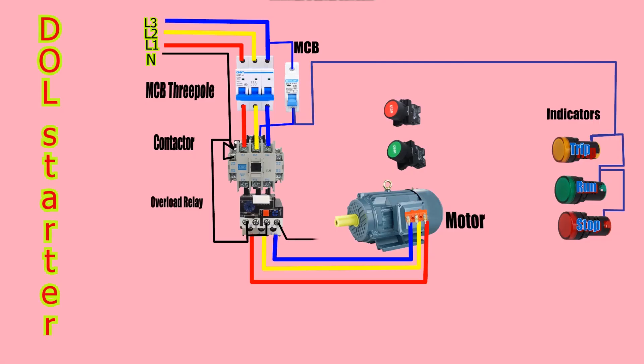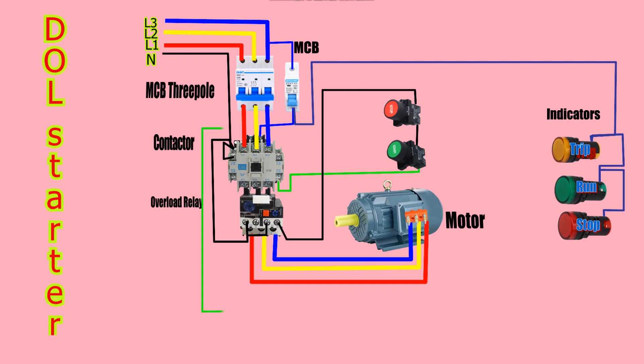The wire from the 96 contacts is connected to the stop push button's first terminal. The second terminal of the stop push button is connected to the first terminal of the start push button. The wire then goes from the second terminal of the start push button to the normally open auxiliary contact of the contactor A1.